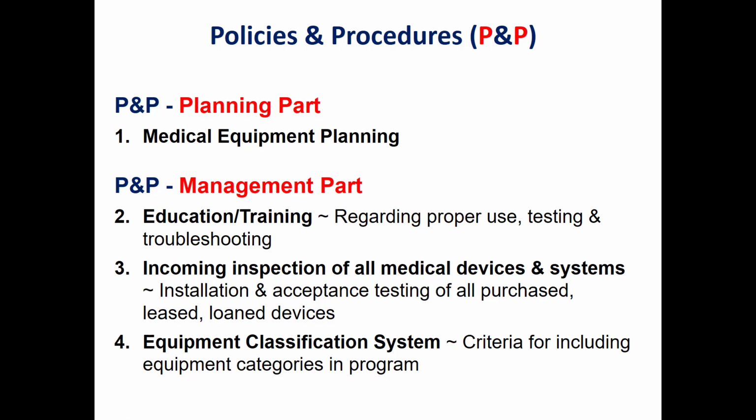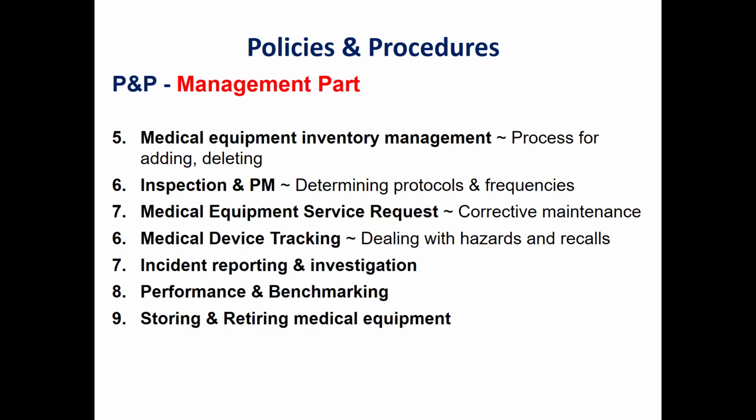One of them is the policy and procedure related to the education and training, and a policy and procedure related to the incoming inspection. In case we have a new medical device, we need to make an incoming inspection. Then I will talk about the policy and procedure related to the equipment classification system, based on which a medical device will be either included or excluded from a preventive maintenance program.